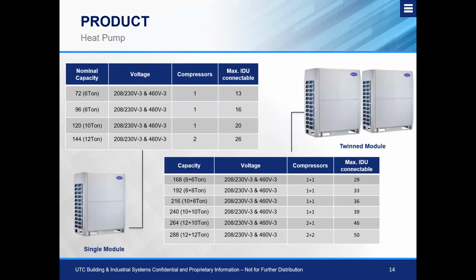Okay, so we talked about heat recovery. Now let's look at the heat pump side of things. So with the heat pump side of things, we no longer have that single base rail, and now we get into the single, the twin, or the triple module, depending on the tonnage that we need for that. On the single module, for the 6 to 10 tons, we have one compressor, and again, on the heat recovery system, as we increase in tonnage, our maximum connectable unit capacity becomes greater as well. Now on the single module, when we move up to the 12 ton, we now add a second compressor, which does increase heating performance and also have that redundancy with that second compressor.